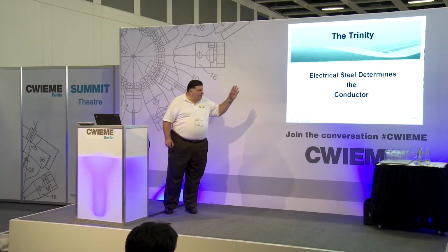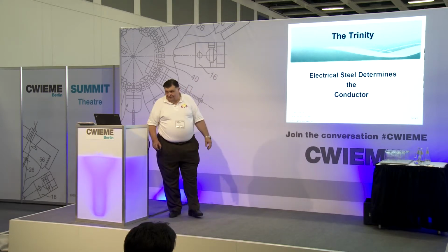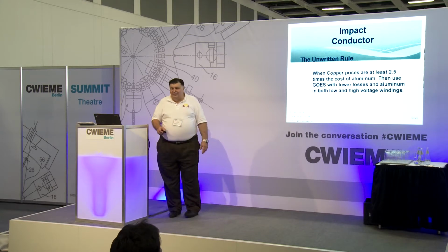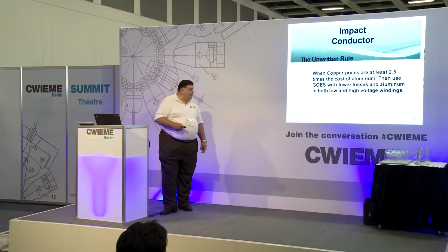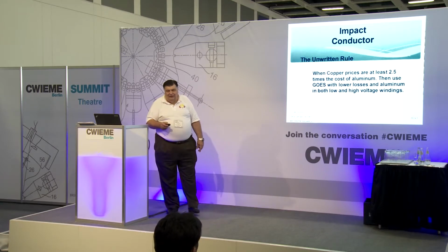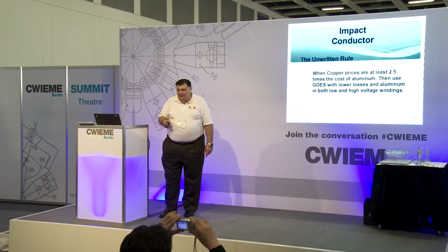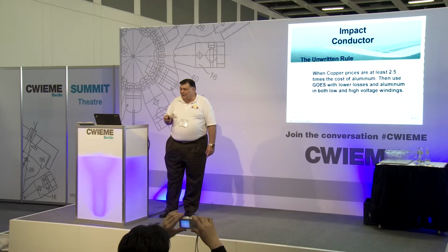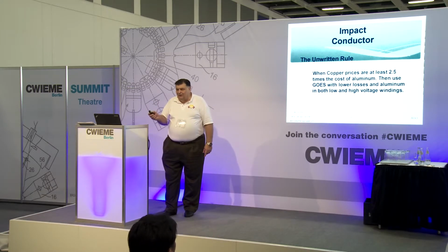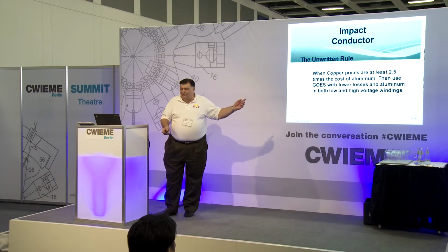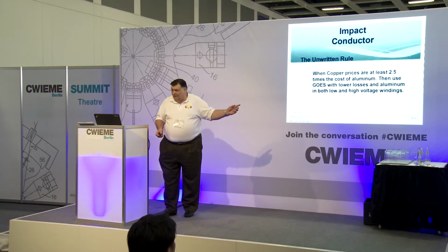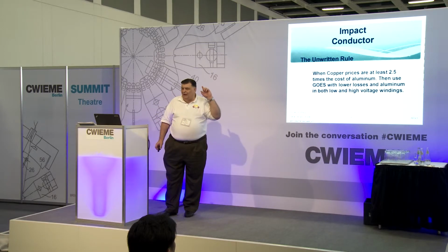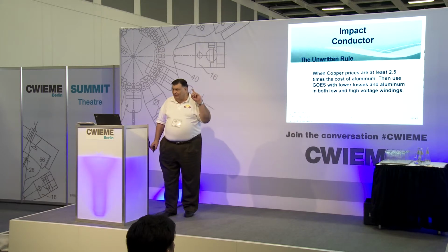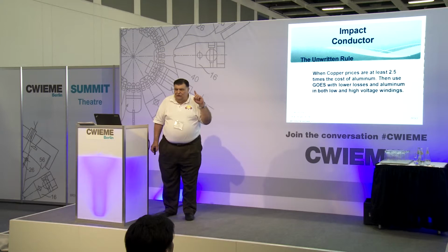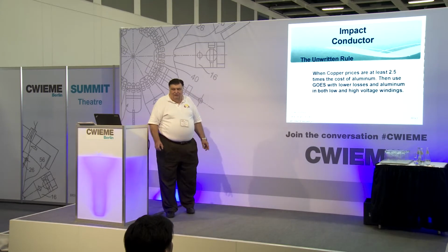In the Trinity, electrical steel determines conductor. There's an old unwritten rule. When the price of copper is at least 2.5 times the price of aluminum, then it is worth it to the transformer manufacturer to look for better grain-oriented steels and use aluminum in both the high voltage and the low voltage. LME closed yesterday. Price of copper was 3.8 times the price of aluminum. So you know where the push is going to be. Use as much aluminum as you can.